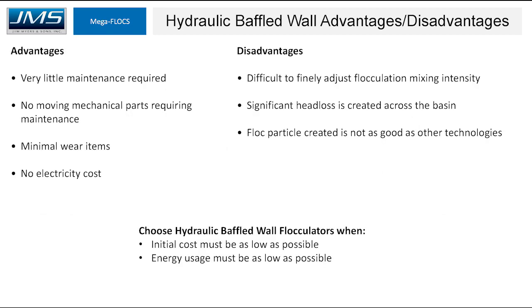The advantages of this type of flocculator are that there is very little maintenance required, no moving mechanical parts, minimal wear items, and no electricity costs. Disadvantages are that it's difficult to finely adjust mixing intensity since all you can control is the flow, there's significant head loss created, and the floc particle produced is not as good as other technologies. You might choose hydraulic baffled wall flocculators when initial costs and energy usage must be as low as possible.